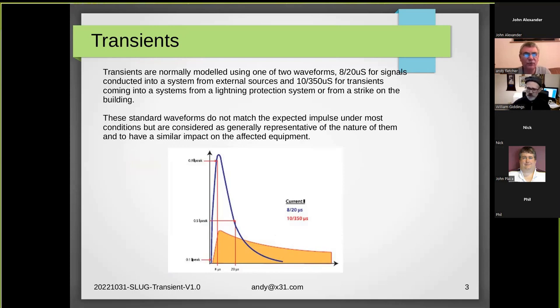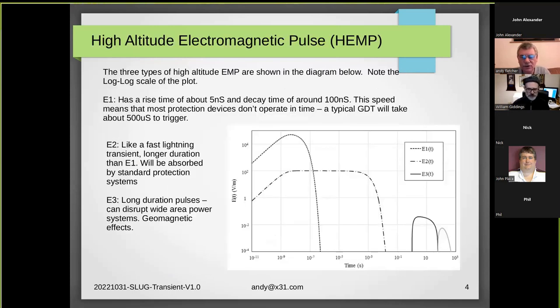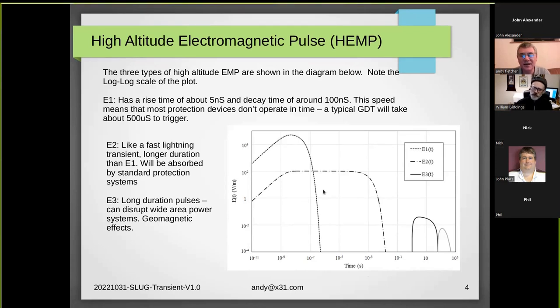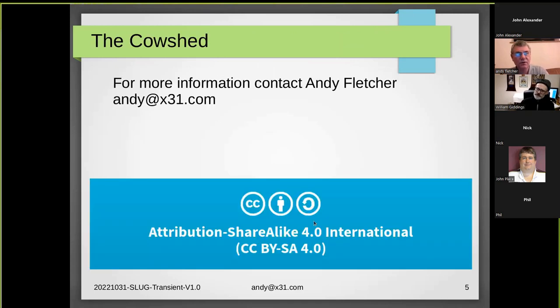Regarding high-altitude electromagnetic pulses (HEMP), you can see three curves on a log-log scale — so it's actually much more severe than it first appears. The E1 pulse has a rise time of a few nanoseconds and decays quickly. The E2 looks more like a normal transient but carries the bulk of the energy — your transient suppression should handle it. The E3 can be several seconds, tens of seconds, or even minutes after the initial pulse.